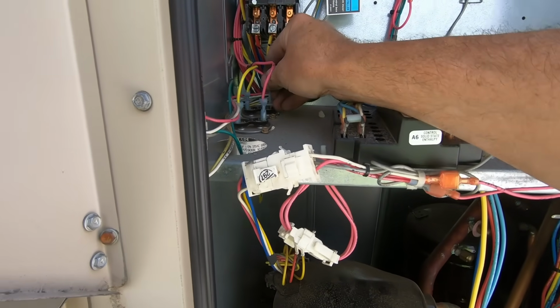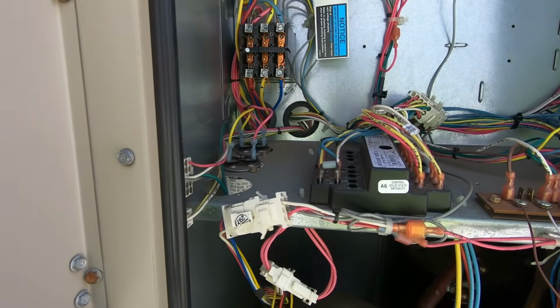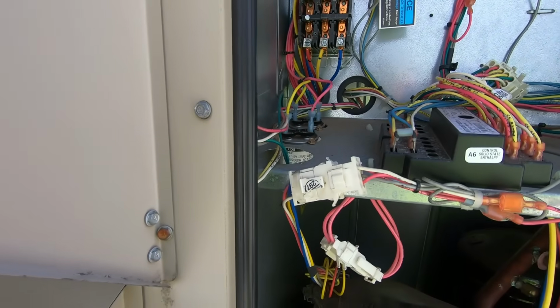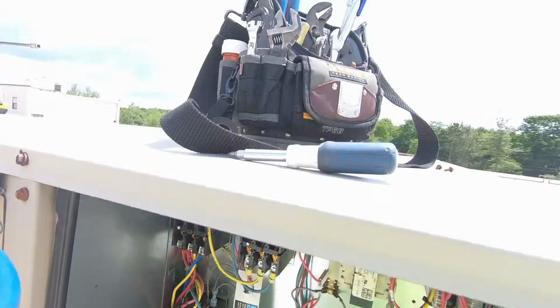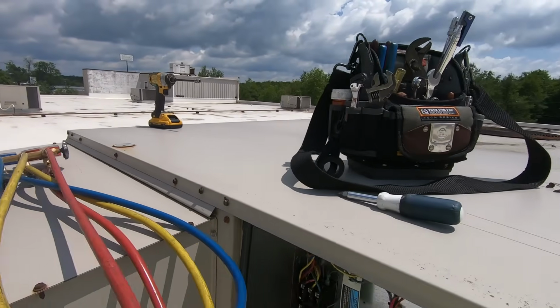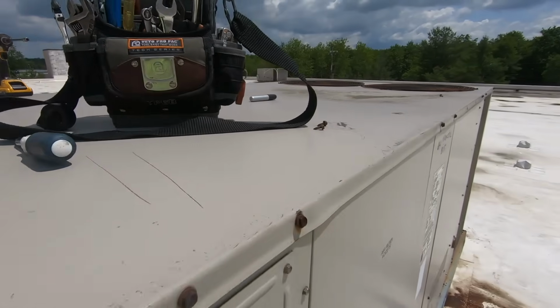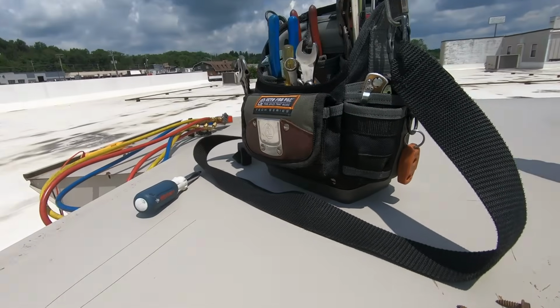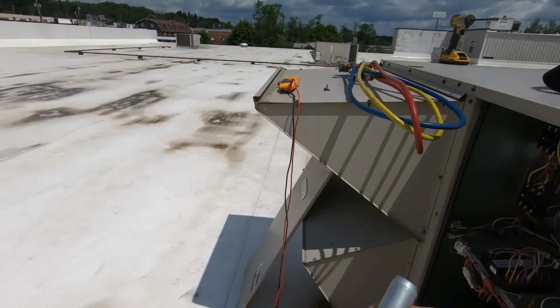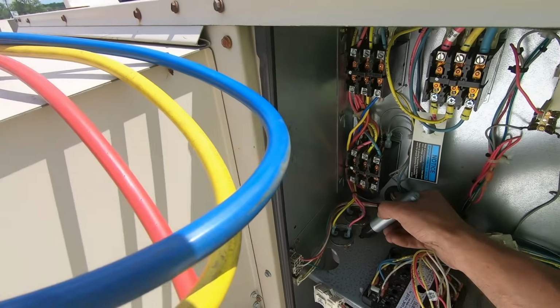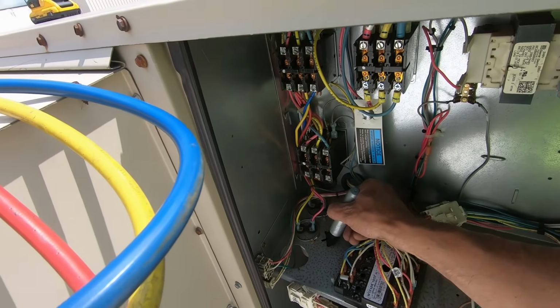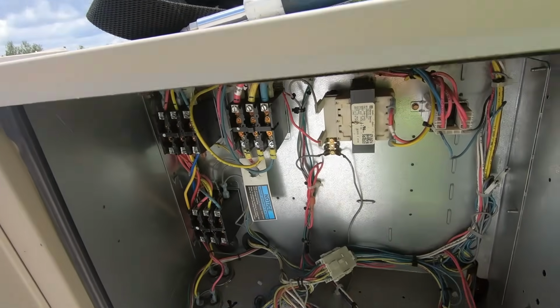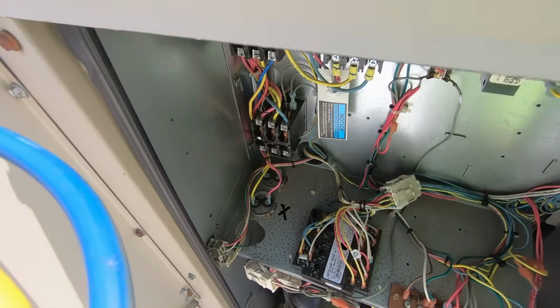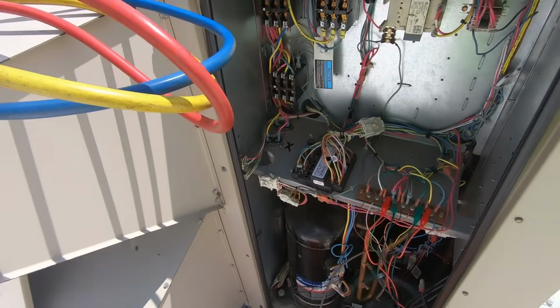So we got a blower rebuild, coil cleaning, filters, belt, 15 MFD capacitor, preventing condenser fan from coming on. And we'll give a little mark next to this one. That way, if someone comes back that's not me, they'll know right which one to replace.